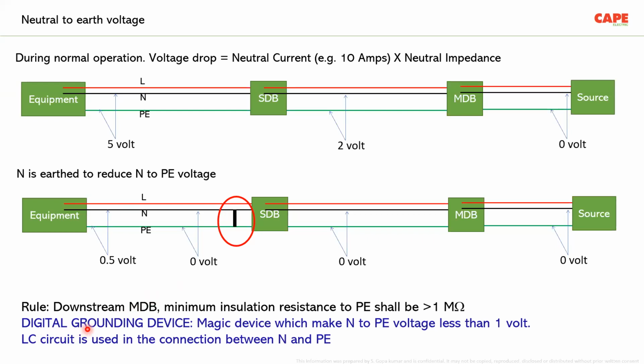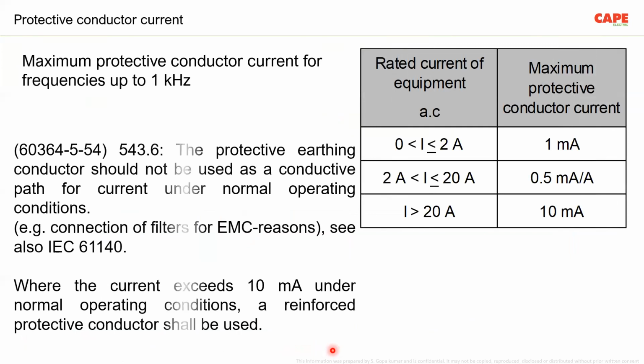The interesting subject now is that there are some gadgets available in the market called digital grounding devices. It's very funny to understand what exactly these devices do. There are some manufacturers, especially from North India, who come with a big story and a beautiful catalog. It's a magic device which makes the neutral to PE voltage less than 1 volt. This is what they claim. They also say they use an LC circuit inside the box to connect between neutral and earth, so this device will absorb the neutral current. This is what they say.